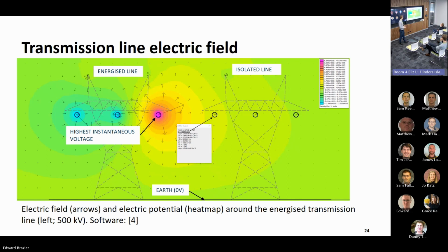At this moment in time, the rightmost conductor on the energized line is at the highest potential. You can see the heat map shows how this affects the potential of each conductor on the isolated line, and the earth is down the bottom, where that shade of green represents 0 volts.